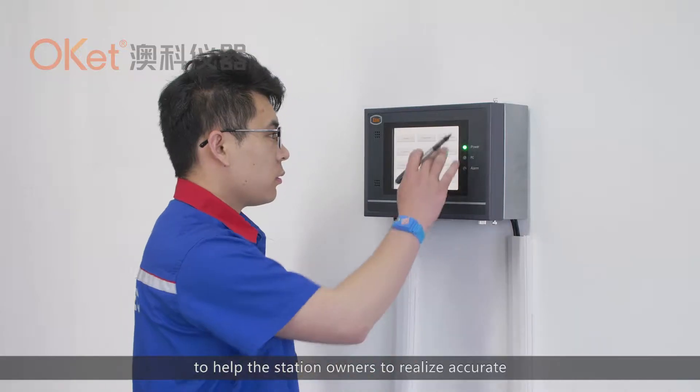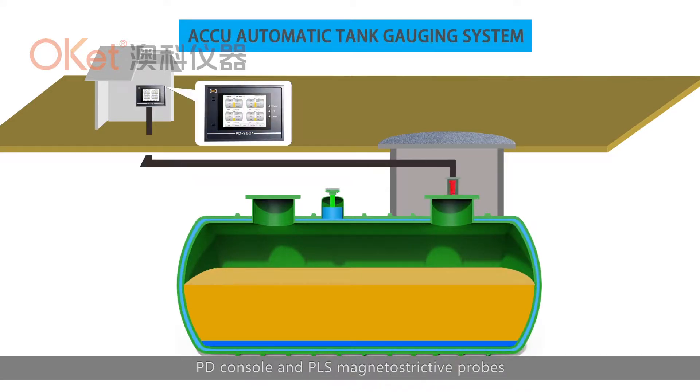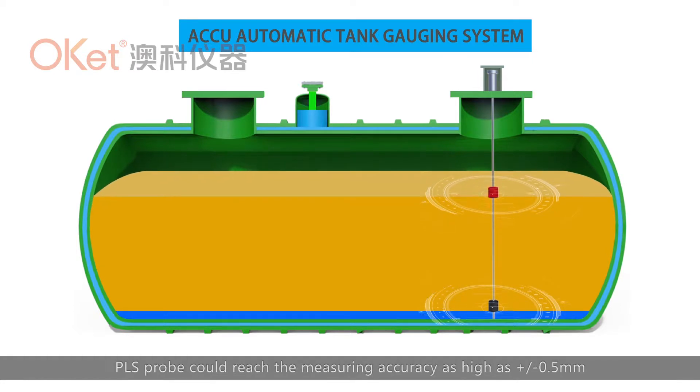ACCU automatic tank gauging system consists of a PD console and PLS magnetostrictive probes. With magnetostrictive technology and our special design, the PLS probe could reach a measuring accuracy as high as plus or minus 0.5 millimeters.